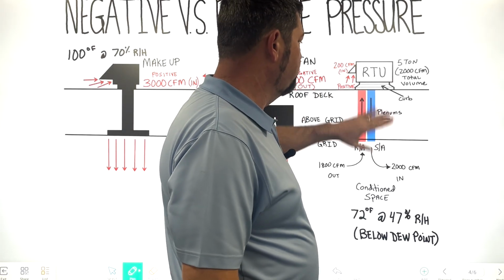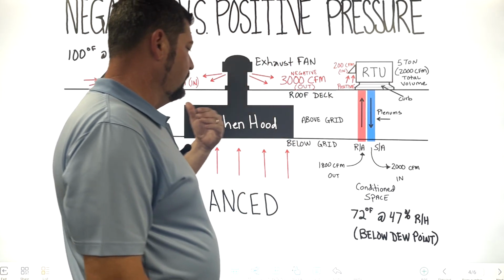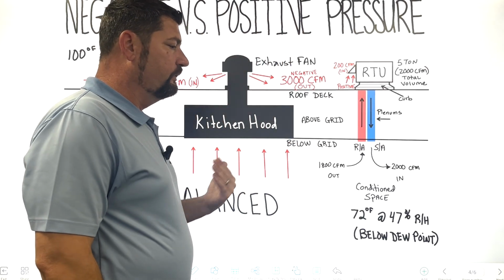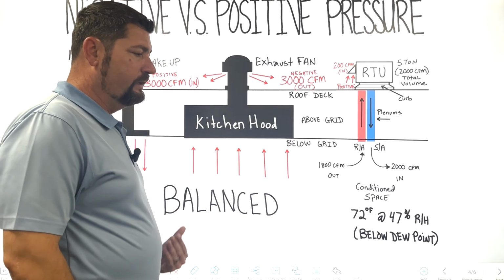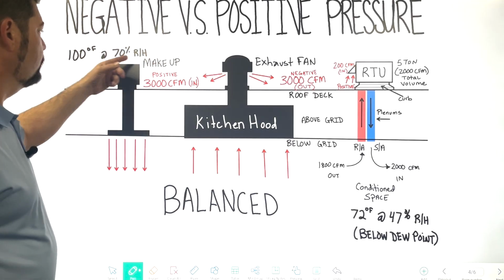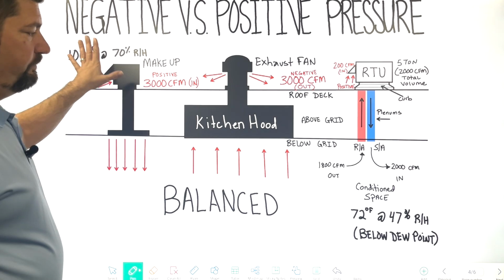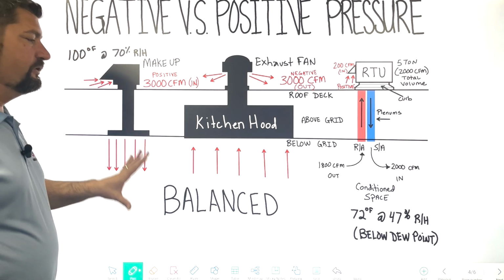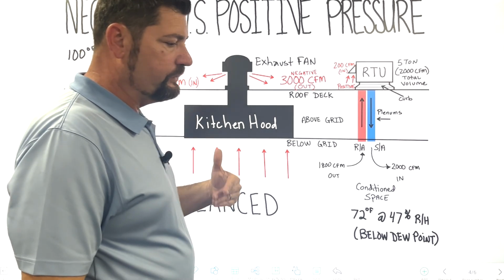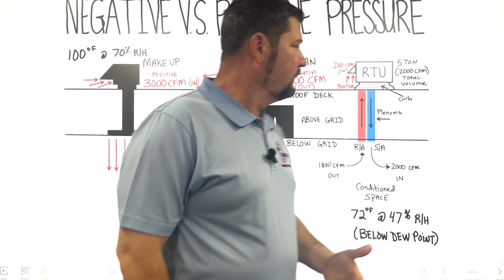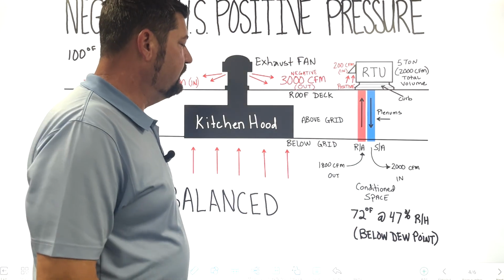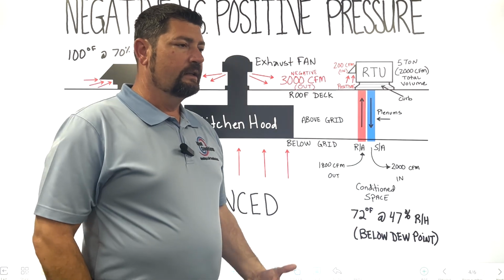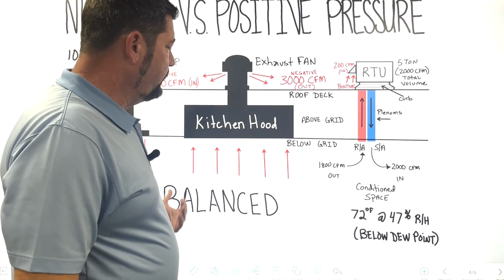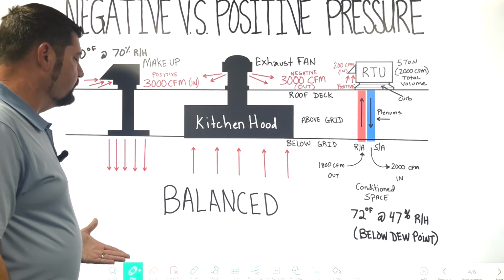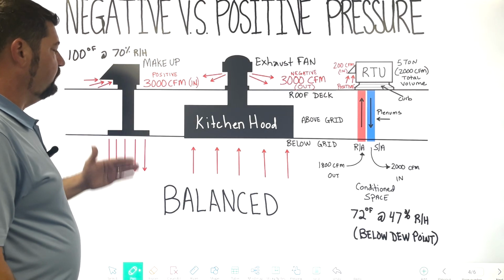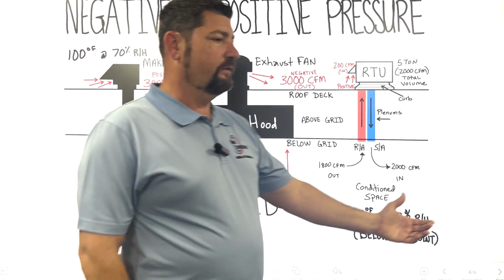You have to have a good balance, and understanding that wherever you're at in the U.S., if you're in an area where there is already a high humidity, like we are here in Florida, then this is a big deal. This is a big concern, and we see this quite often. Maybe out west or up north, if the humidity is less, take advantage of some free air conditioning. It's not really going to hurt anything. If I was out west where it was drier and warmer, I would still want to have this balanced, because I don't want to invite heat inside, right?